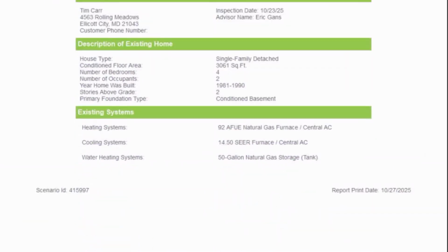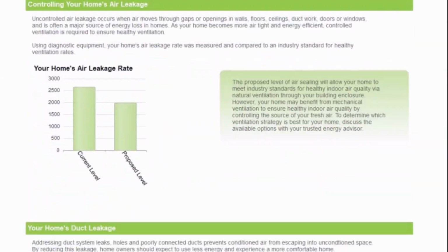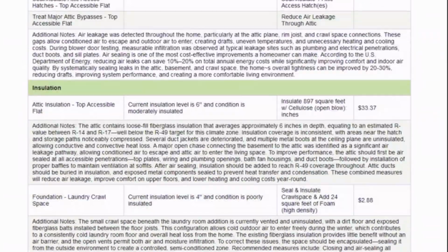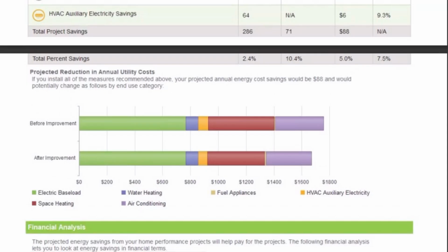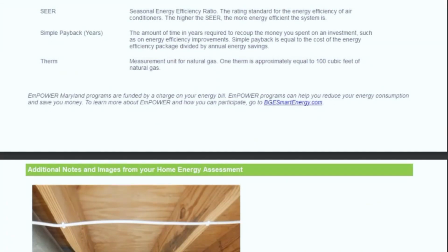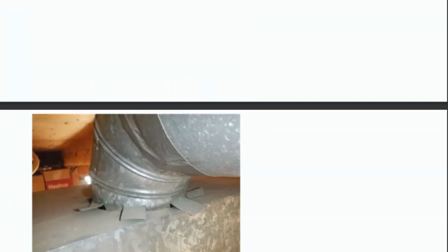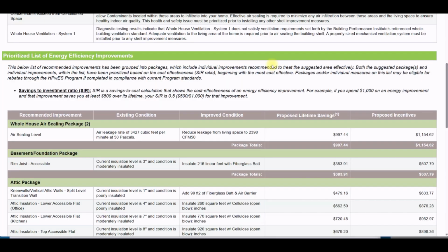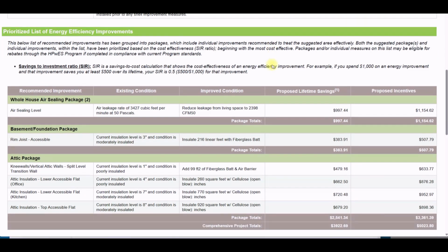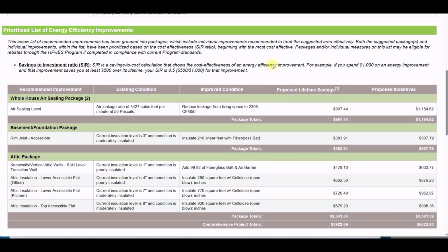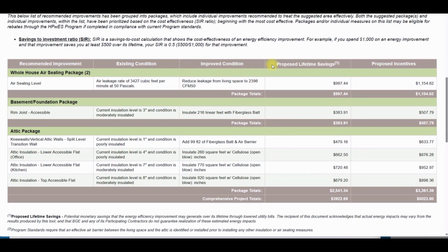Here's a look at how that all comes together for the homeowner. The photos, test results, and modeled savings translate into a clear plan. Primary measures first, then optional upgrades like cantilever insulation if floors remain cold. The report also outlines utility incentives and their expected out-of-pocket costs so they can see exactly what's available before deciding on next steps. That's the power of combining field diagnostics with modeling.